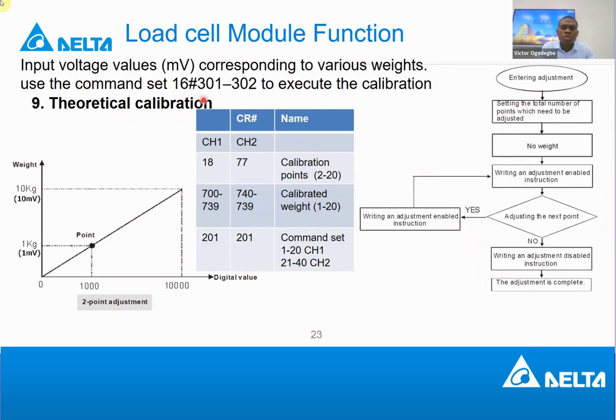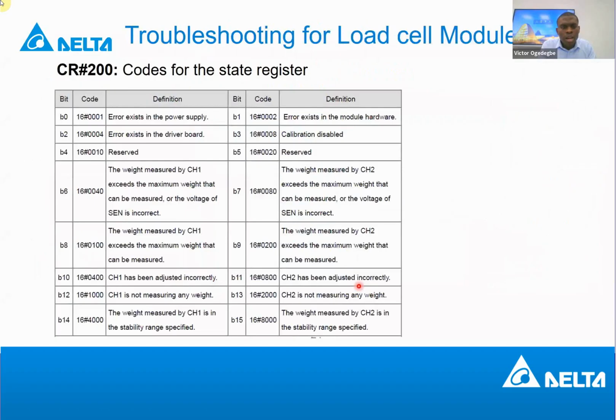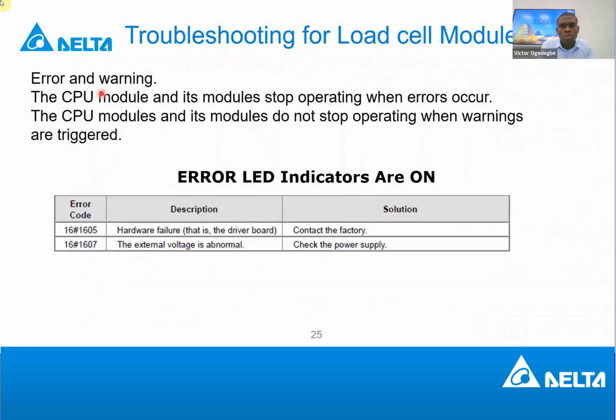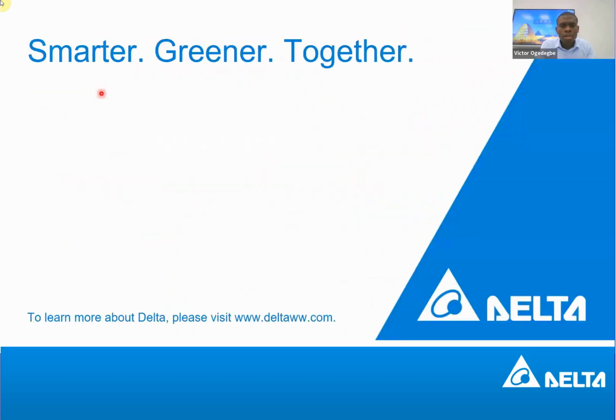So once you calibrate this, the digital value of your load cell module corresponds to the analog signal that your sensor has measured, and then you can play around with it in your application. This is it. And another important thing, which I told you before: control register 200, each bit error code is here. And in the manual, you'll find other error code information that could be helpful to your application.